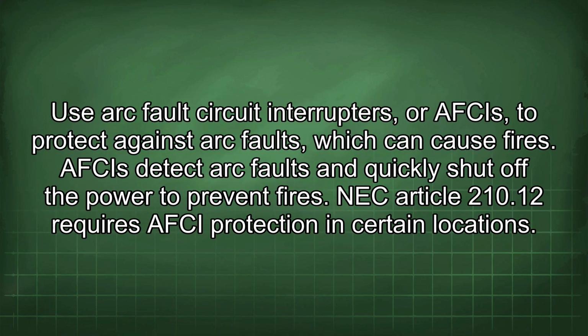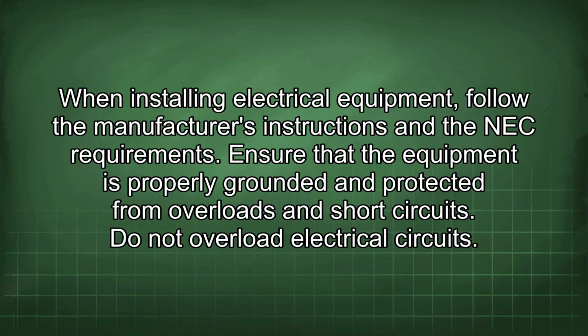Use arc fault circuit interrupters, or AFCIs, to protect against arc faults, which can cause fires. AFCIs detect arc faults and quickly shut off the power to prevent fires. NEC Article 210.12 requires AFCI protection in certain locations. When installing electrical equipment, follow the manufacturer's instructions and the NEC requirements. Ensure that the equipment is properly grounded and protected from overloads and short circuits.